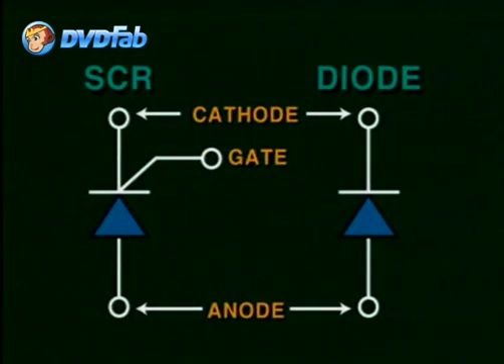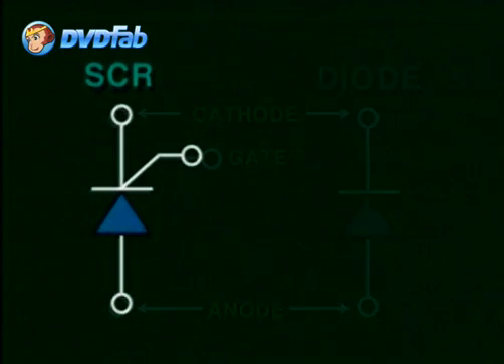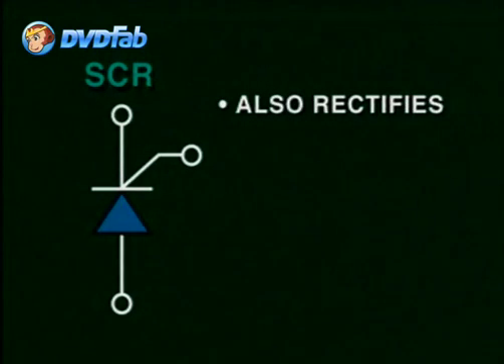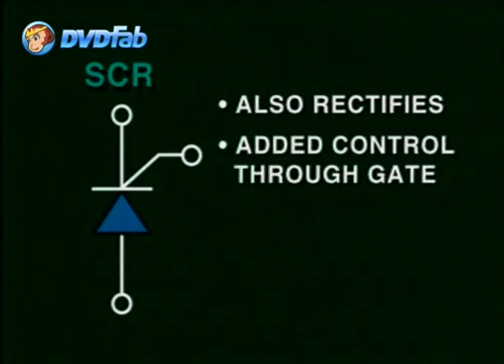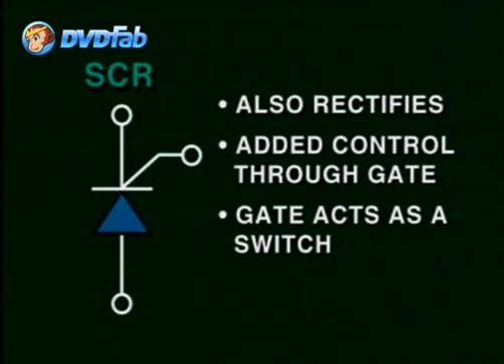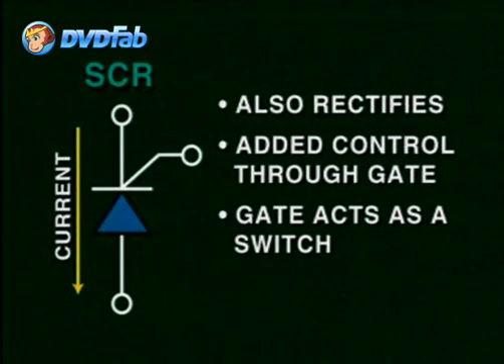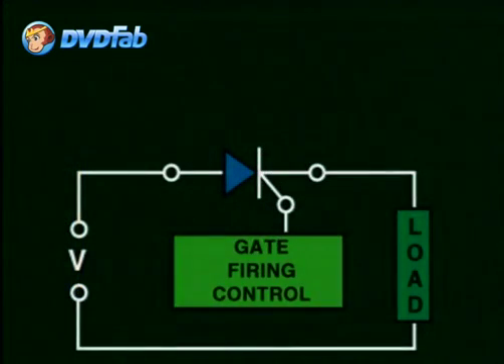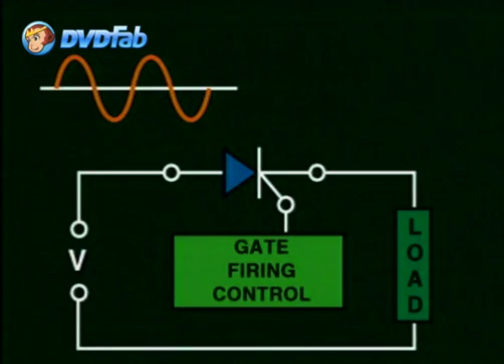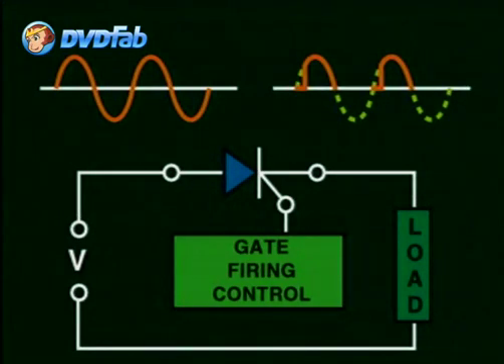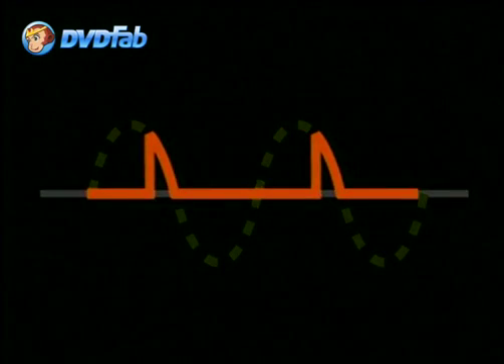As you can see, it is very similar to the diode, which is used to rectify AC voltage into DC voltage. In fact, SCRs function very similarly to diodes as far as rectification is concerned. SCRs, however, provide added control through the gates. The gate essentially works as a switch which allows current passing from the cathode to the anode to turn on and off. This control allows the SCR to turn on at any point in the half-cycle rectification from full to partial conduction of voltage. The firing circuit controls the amount of voltage conduction of the SCR by controlling the gate.